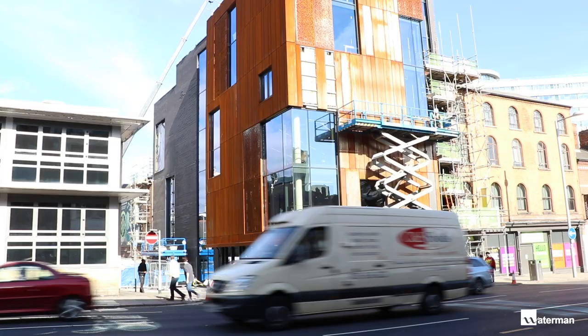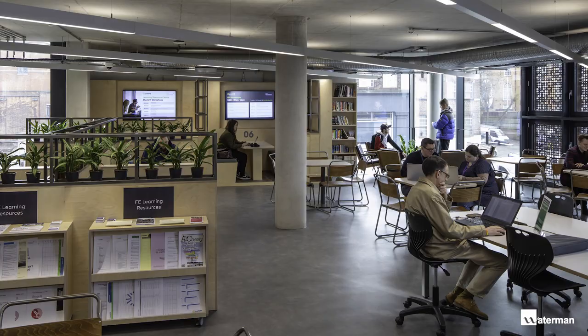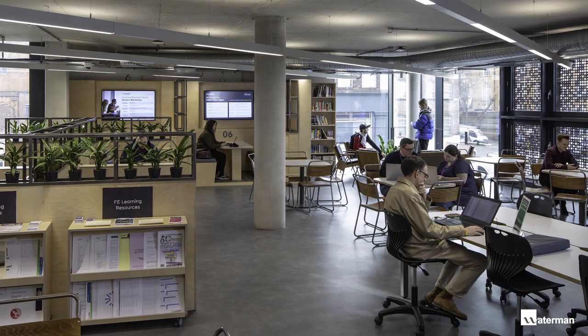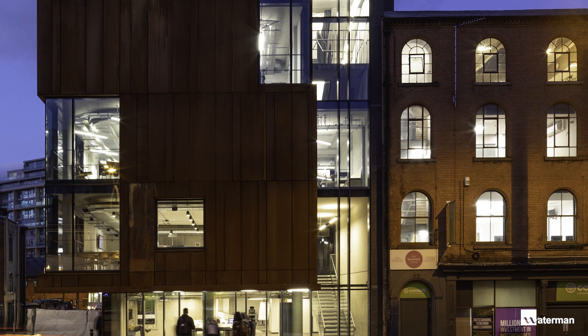The Confetti building really allowed us to push the envelope of what we can do with environmental buildings. We're looking to take as many systems out of it as possible and only apply systems that have any form of energy intensity into those areas which can't be dealt with in any other way. Combining highly sealed facades but with very low demand led ventilation systems, for example. What that means is that we're delivering the minimum amount of air throughout the whole building all of the time, but matching the loads within the building to where they were using the building the most.